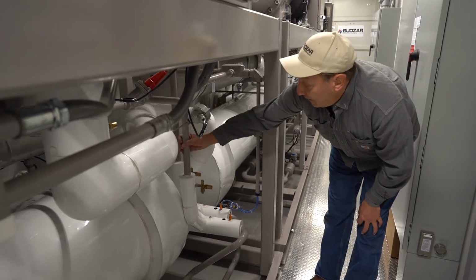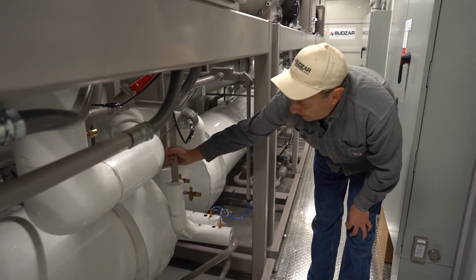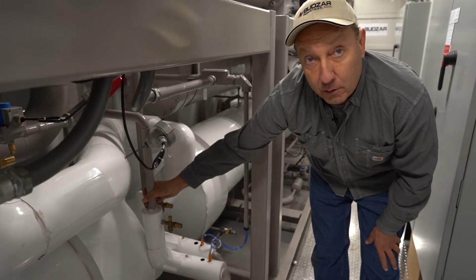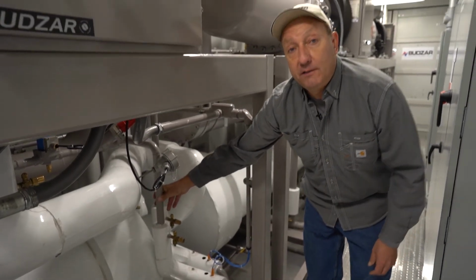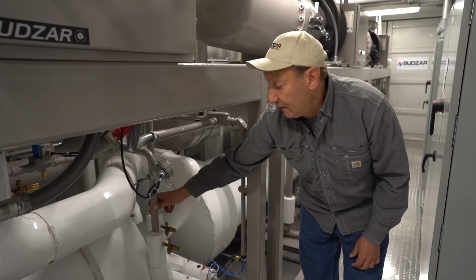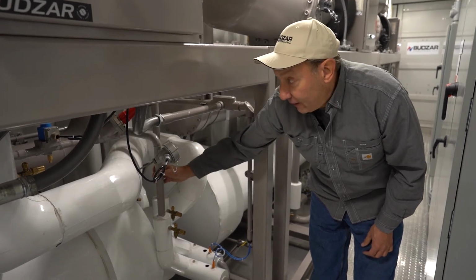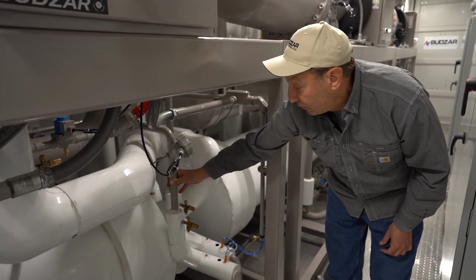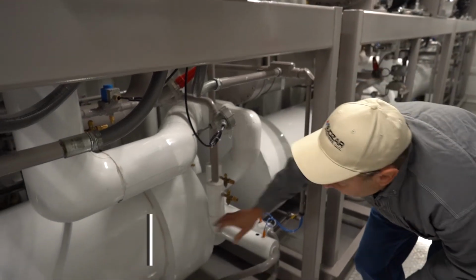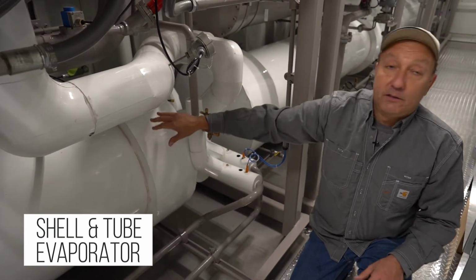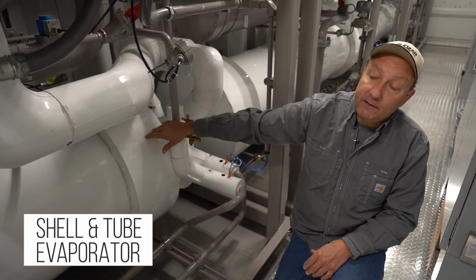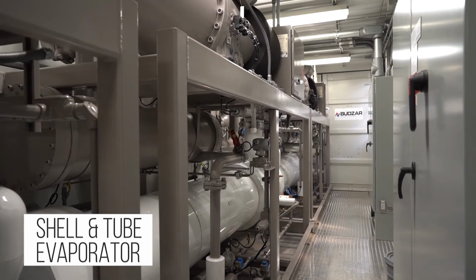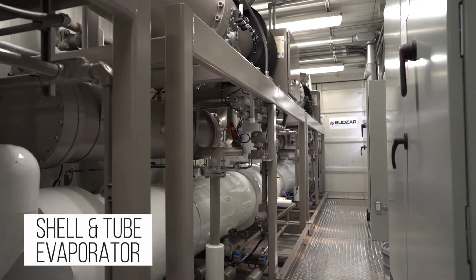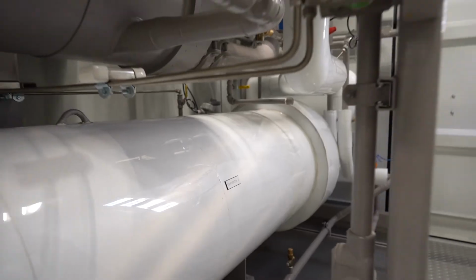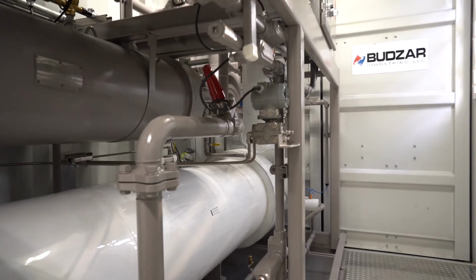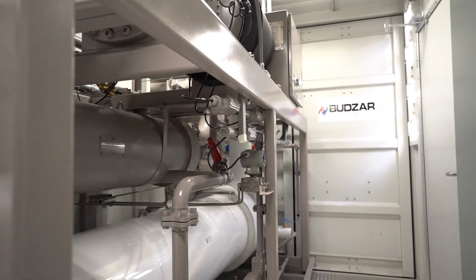Then this is our hot gas bypass lines. We have capacity control. We unload from full capacity, 25 to 100%, and we have hot gas bypass also for capacity control. This is our shell and tube evaporator. It's a dual circuit evaporator. The glycol comes in one side and comes out cold on the other. This is where the cooling or chilling is done. This system is designed for 20 degrees Fahrenheit leaving fluid temperature.